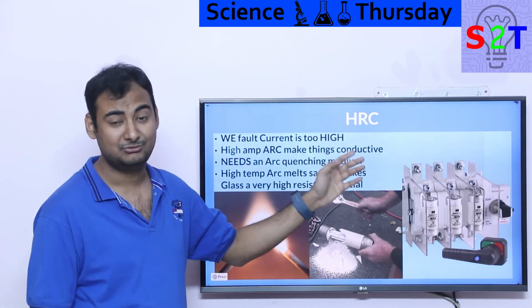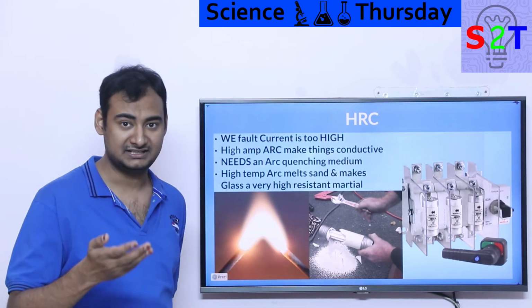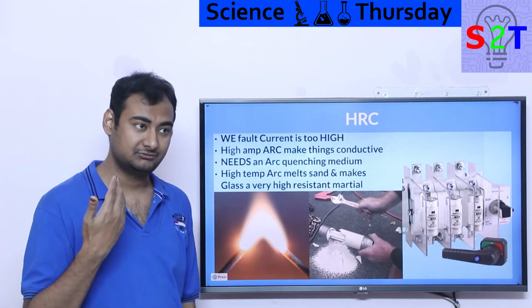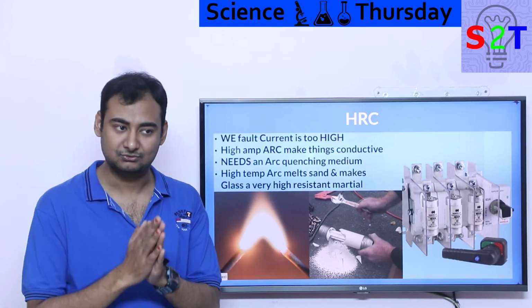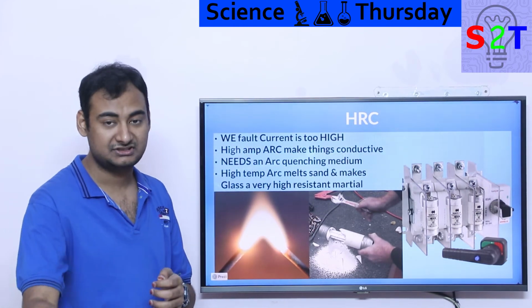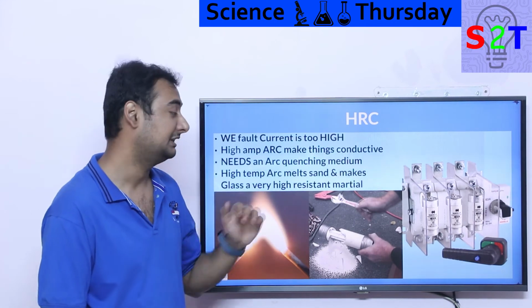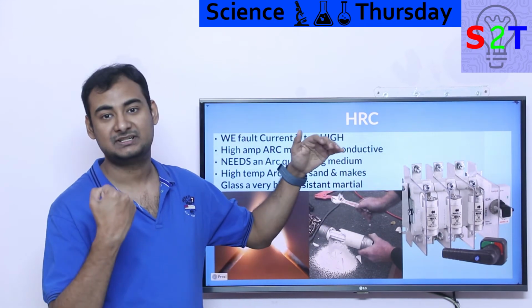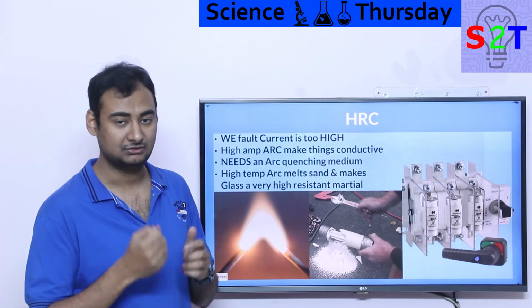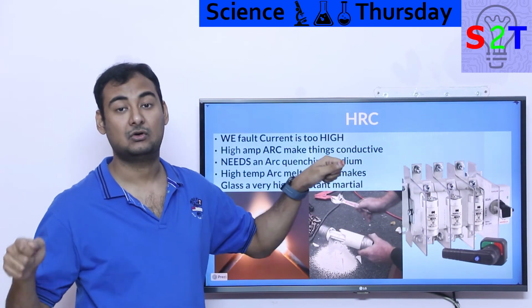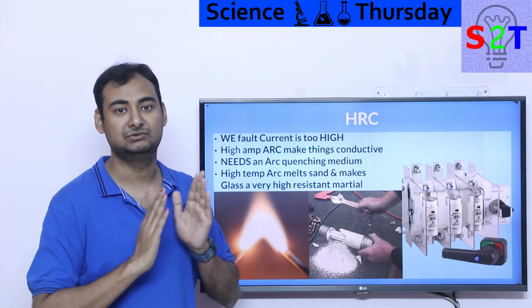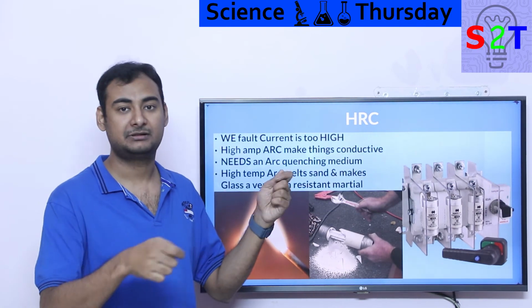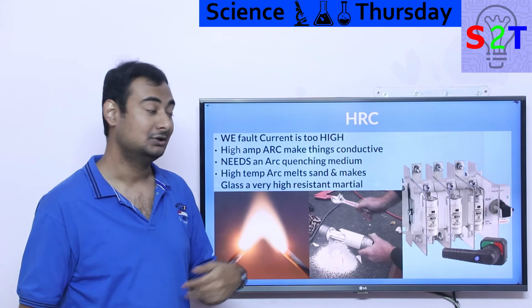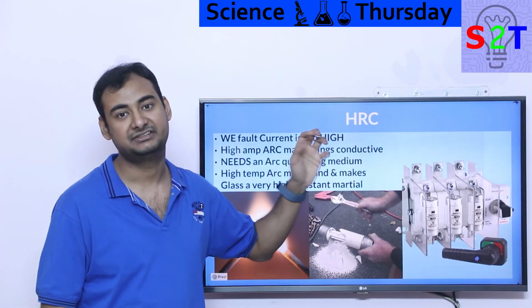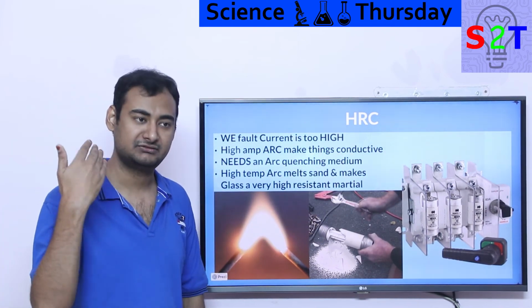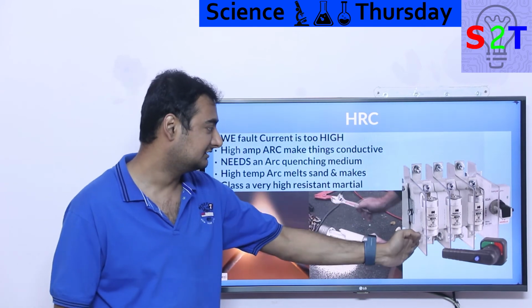So the idea with that is, the moment you have one fault in one phase, if you let it be, now the 2 phases are running the load, it will become unbalanced basically instantaneously. You want to disconnect all of it. You have one fault, you disconnect all 3. In certain loads you have to do that. In those sorts of scenarios, the plunger basically triggers a disconnecting device. So you could have a fault in one phase, it disconnects the remaining 2 phases, so everything is safe. You do not have, okay, one tripped, then another tripped, then another tripped, because that does happen if you have a fuse that blew up but did not trip the other device, because over time that overcurrent event will destroy everything else. And you may find they are protected with shields.